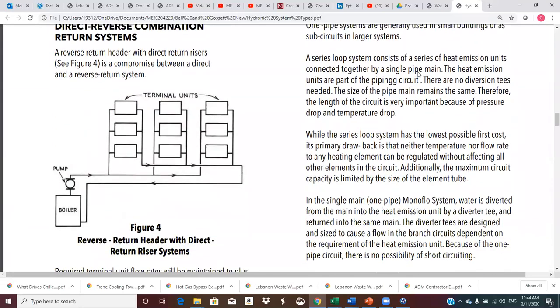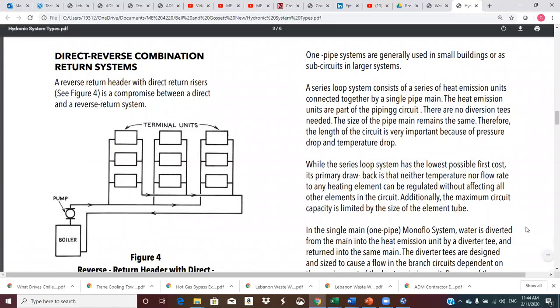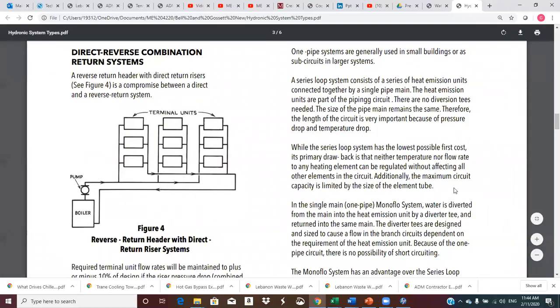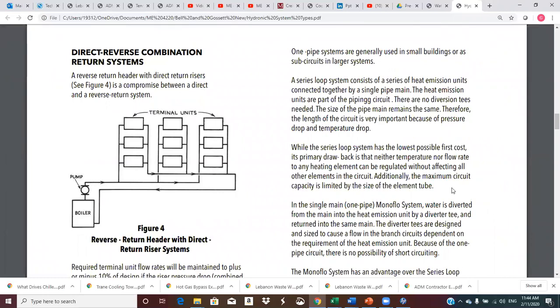Okay. This would be, let me make that just one smaller. This would be a direct reverse combination. So let's see, this is a reverse return header with direct return risers. So the header, the main distribution piping, is reverse return, because here's our short path going up into this riser. And then when we come back out of the riser, we go all the way down here and all the way back. So that's definitely reverse return.